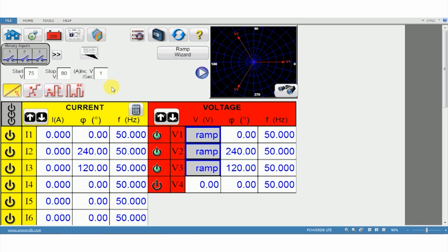The time delay is configured as instantaneous, that is 0 seconds. And it should approximately operate at 120%, near around 76. So let's find out by running the test. Let's see the settings before we do that.